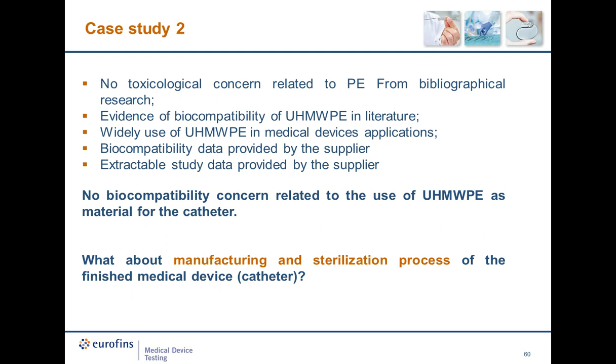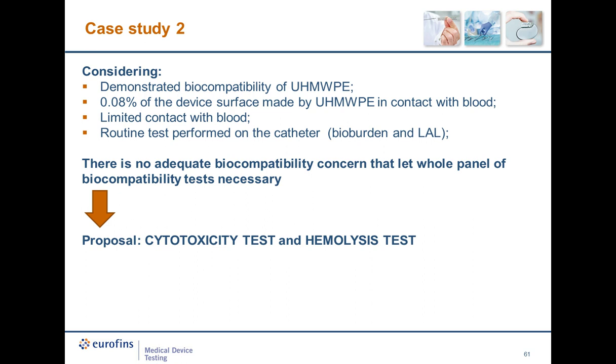But what about manufacturing and sterilization process of the actual finished catheter? Our strategy addressed this question. On the basis of the considerations summarized here, the fact that raw material is biocompatible, less than 0.1% of the device surface made with the new material is in contact with blood, and in any case, the contact is limited, and routine tests such as bioburden determination and endotoxin tests are performed on the finished device, the test strategy was limited to cytotoxicity test and hemolysis test. Compared to the checklist approach, this strategy reduced the number of tests required, saving time and money. This strategy was accepted by the competent authority.